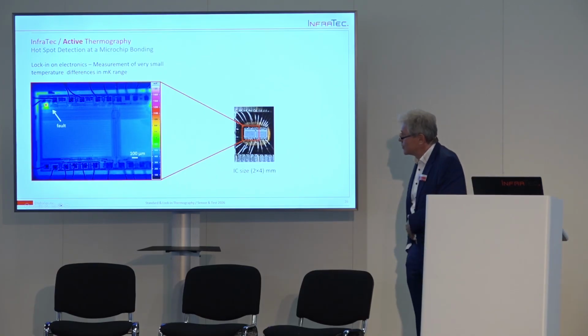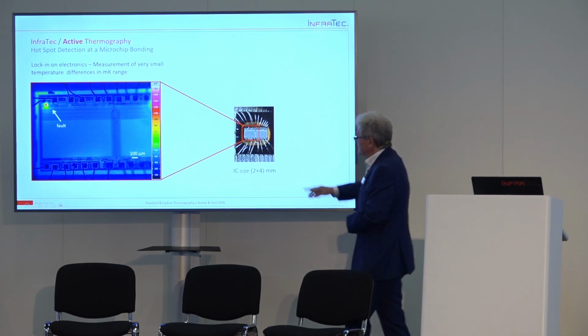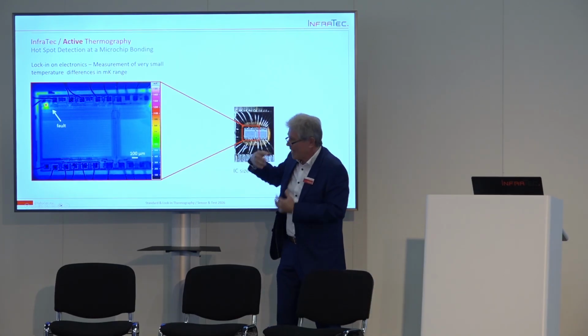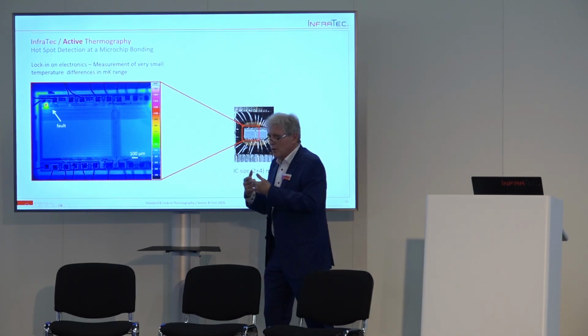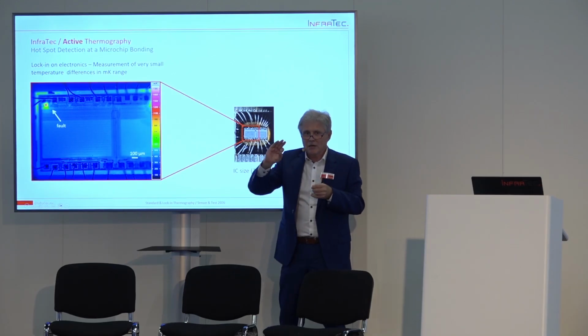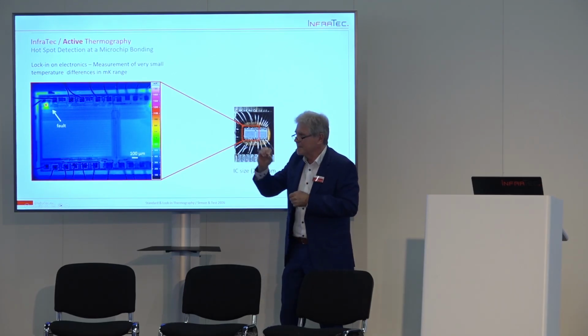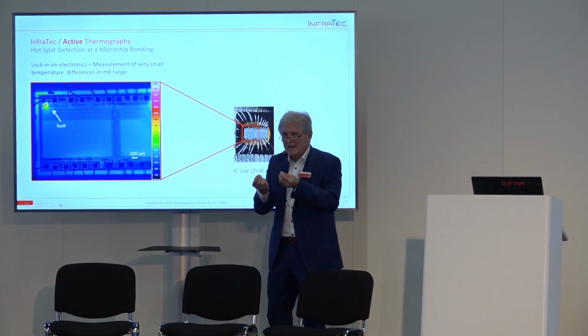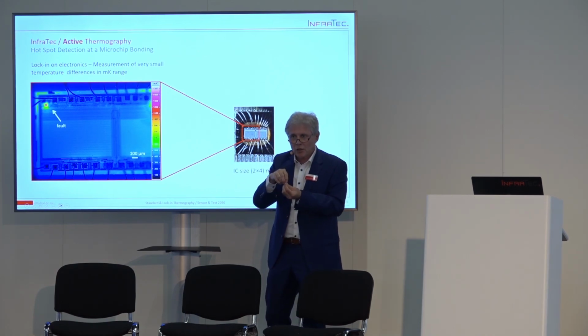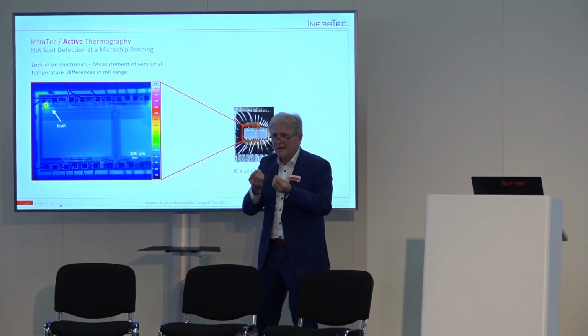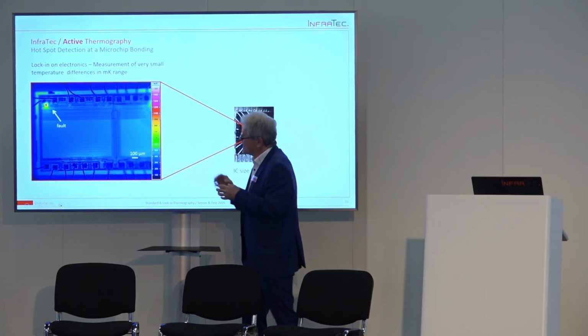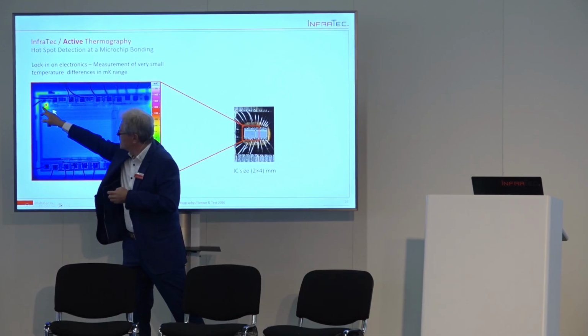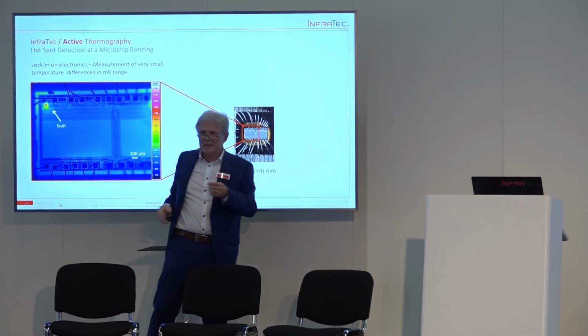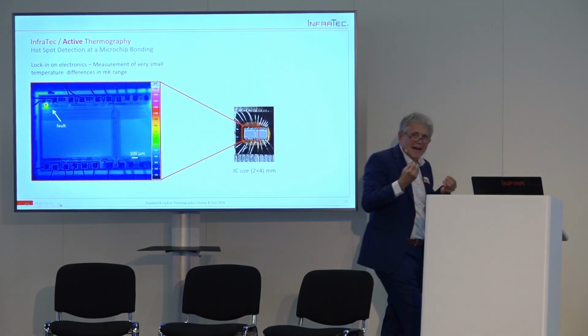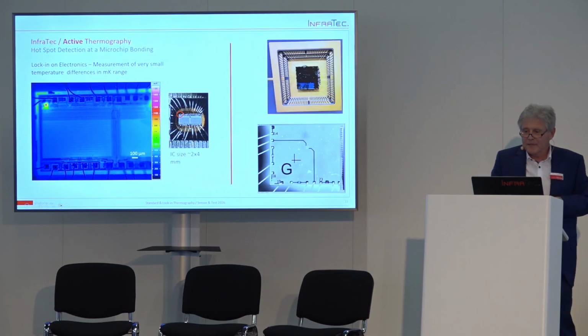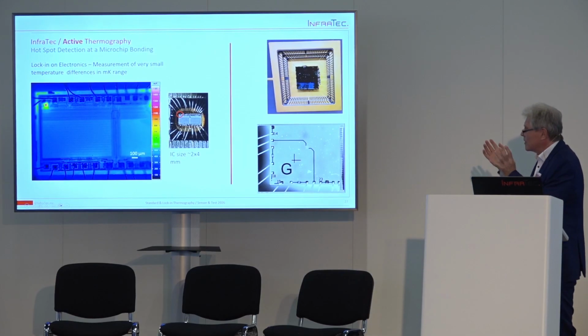Or when you look at a chip surface, when you see here the chip, with a standard thermography, you won't see any difference because the thermal signal is often so low, or the emissivity factor of the object is so low, that you cannot see anything. You cannot see any faults and so on. But with active thermography and with the lock-in procedure, then you can see that there's a small difference, and it can be a hint to a fault. Okay? So it can look like that.